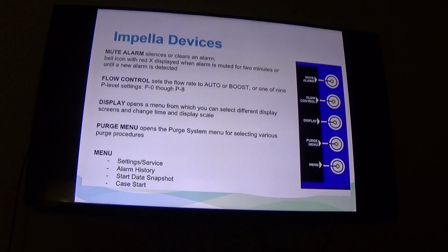Your flow control, this is that P level that I was talking about. You can select from P0 all the way to P8. P0, 1, and even 2 are kind of used for insertion and removal. Really, the patient should not be on these, and if they are, you really need to question why. Because if the P level is less than 2, you're actually going to start getting retrograde flow down the Impella. So that's not actually a good thing.